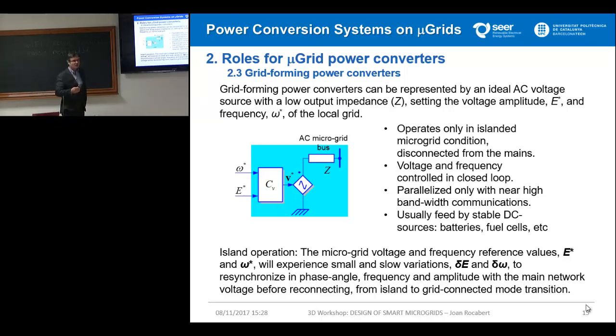Once the grid is restored, or once the microgrid central controller wants to connect again to the grid, both elements should be resynchronized. The central controller, observing the two voltages, can give a delta E and a delta of frequency, omega, to make the resynchronization and connection again to the main grid. In that moment, that converter should immediately pass again to work as a grid feeding converter.